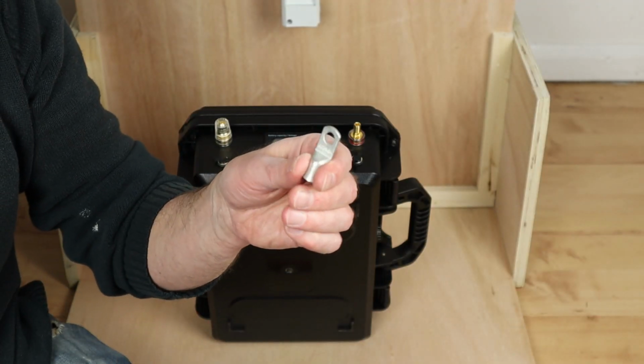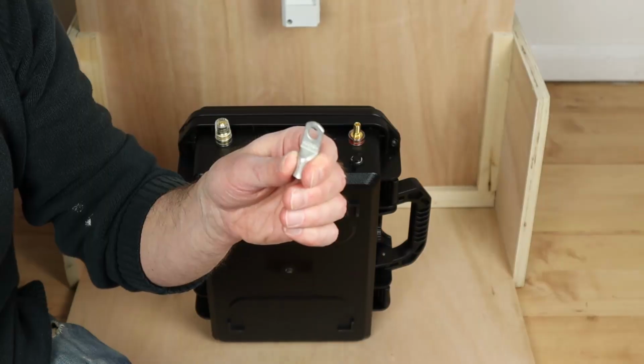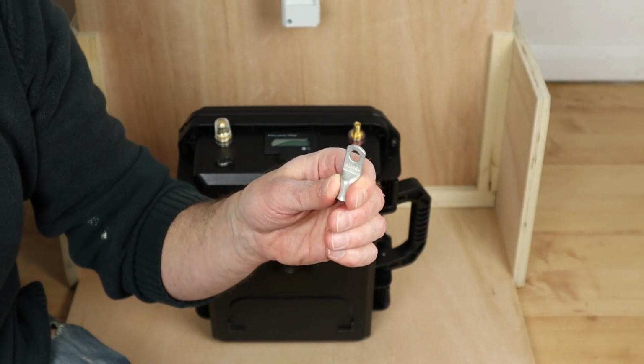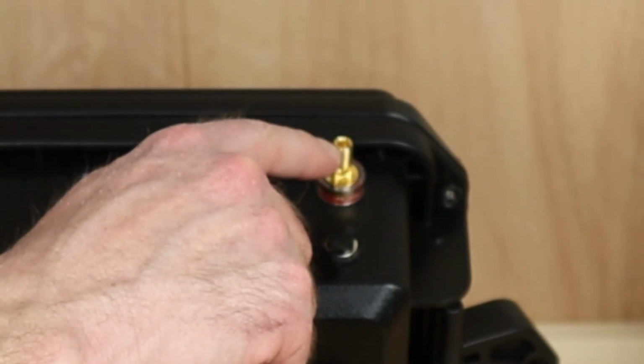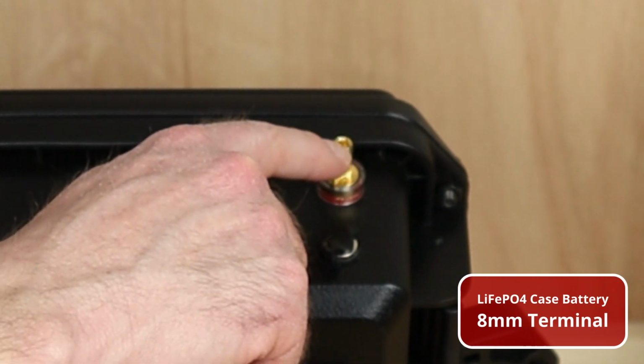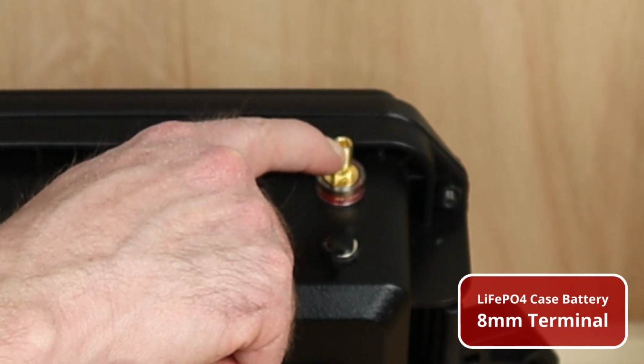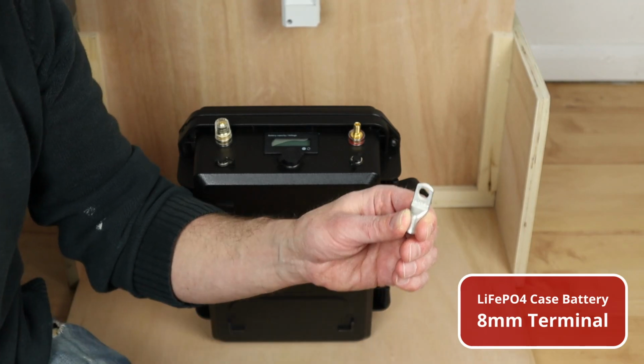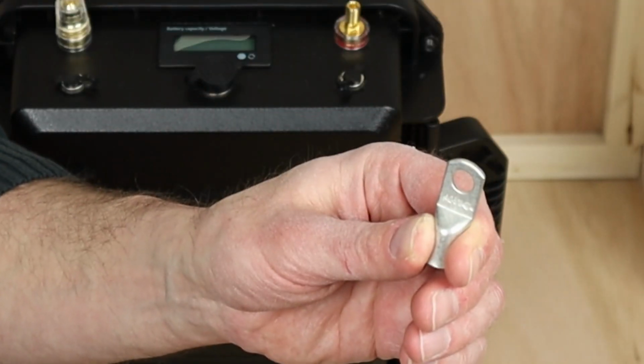The second thing you need to consider is the size of the hole - this relates to the terminal you're going to connect it to. In this case this is an 8mm terminal, and you can measure that - I suggest doing it with something plastic just to check what size hole would be best. So you've got your two key indicators there and the size of lug you want.